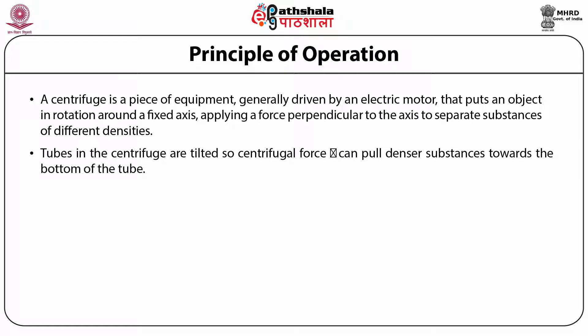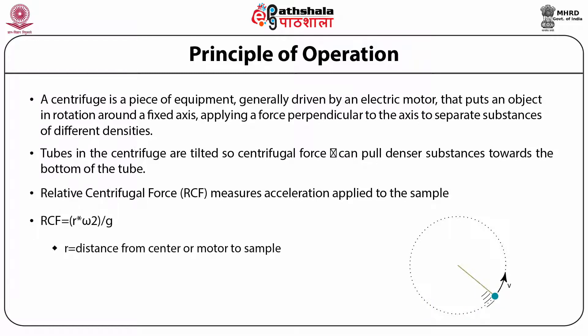We will discuss the principle of operation of centrifugation technology. The centrifuge is a piece of equipment driven by an electric motor that puts an object in rotation around a fixed axis, applying a force perpendicular to the axis to separate substances of different densities. Tubes in the centrifuge are tilted so the centrifuge can pull the denser substance towards the bottom and the lighter substance to the top. There is an equation: RCF = R × ω² / g, where R is the distance from the center of the axis of rotation, ω is the angular velocity, and g is gravity (9.8 m/s²).